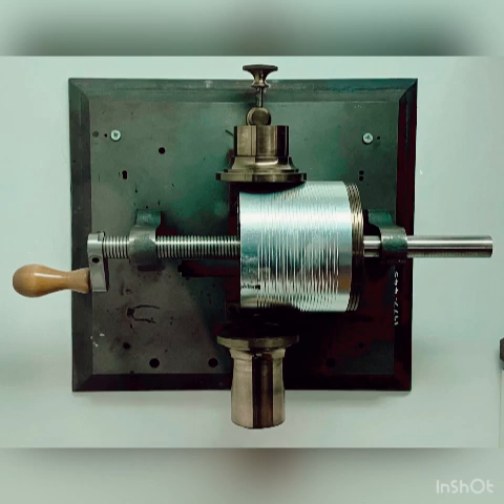Artificial ear is a device for loading an earphone with an acoustic impedance which simulates that of the average human ear, used for measuring the sound pressure thus developed. Fitted with a 6cc coupler, it's used to calibrate an audiometer and its AC headphones. An artificial mastoid is a device for loading a bone vibrator with a mechanical impedance which simulates that of the average human mastoid, and measures the vibration so produced. It can be used to reproduce frequency response charts for a bone conduction hearing aid, or to calibrate an audiometer and its bone conduction unit. Sound level meter: a reference scale, special weighted scale, high and low pass filters. Reference level of the A scale is the human equal loudness contour for hearing faint sounds.